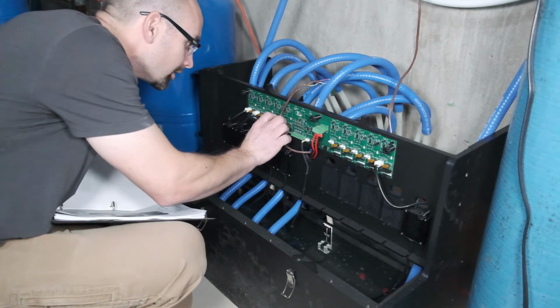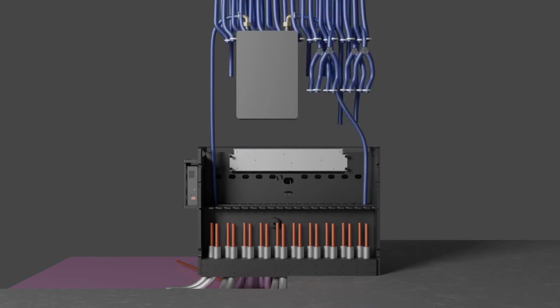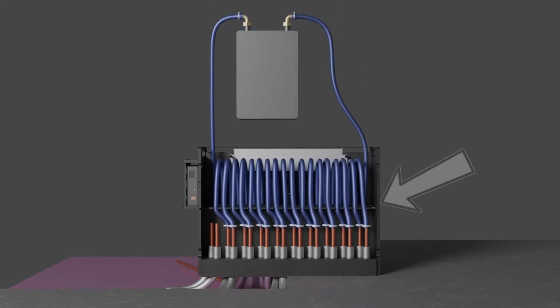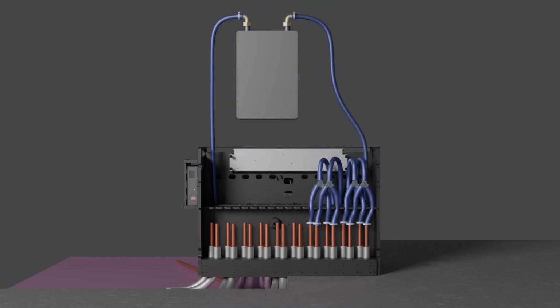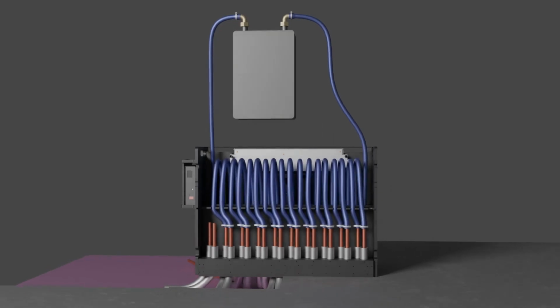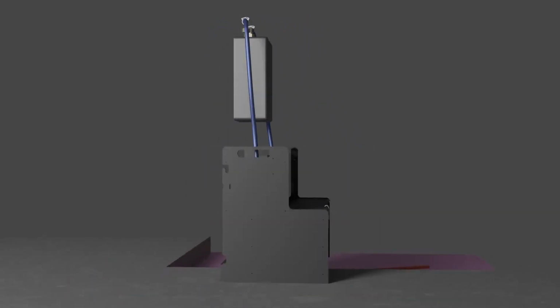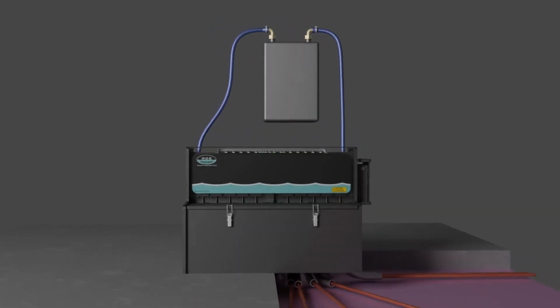Usually those settings end up as follows. Low. This is adequate for most single loops. Medium. This is for pumps that have splitters with two loops. And max. This is for heat sources.